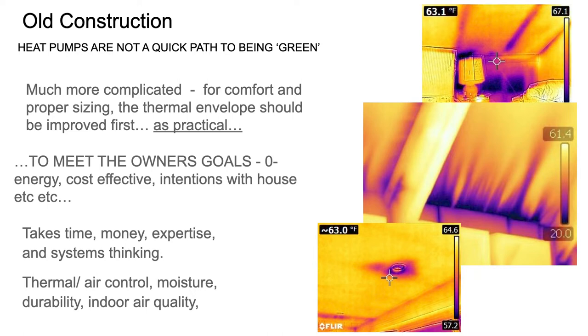Every new home should have heat pumps. Old construction is complicated — you've got to be wary of just throwing heat pumps in old houses. For example, if you have an old house with an old oil boiler in the basement, that thing is ancient, but the basement is the warmest room in the house because there's so much heat coming off that boiler. You can't just throw heat pumps in thinking you'll swap out that system, because your basement's going to get even colder and wetter, leading to other issues. All these infrared pictures are from houses where people wanted to convert to heat pumps and had major thermal boundary flaws that need to be addressed first. You really have to do envelope upgrades — what is practical depends on cost, long-term goals, and your resources.